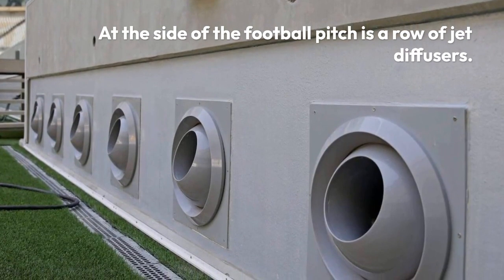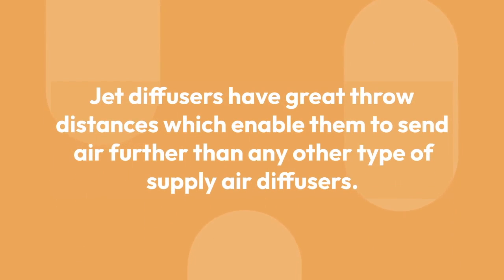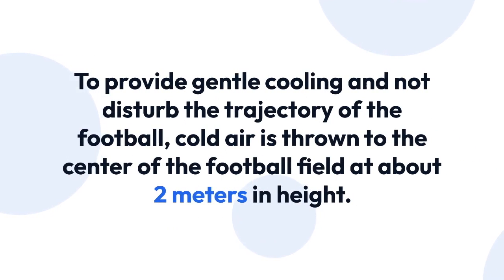At the side of the football pitch is a row of jet diffusers. Jet diffusers have great throw distances, which enable them to send air further than any other type of supply air diffusers. To provide gentle cooling and not disturb the trajectory of the football, cold air is thrown to the center of the football field at about 2 meters in height.